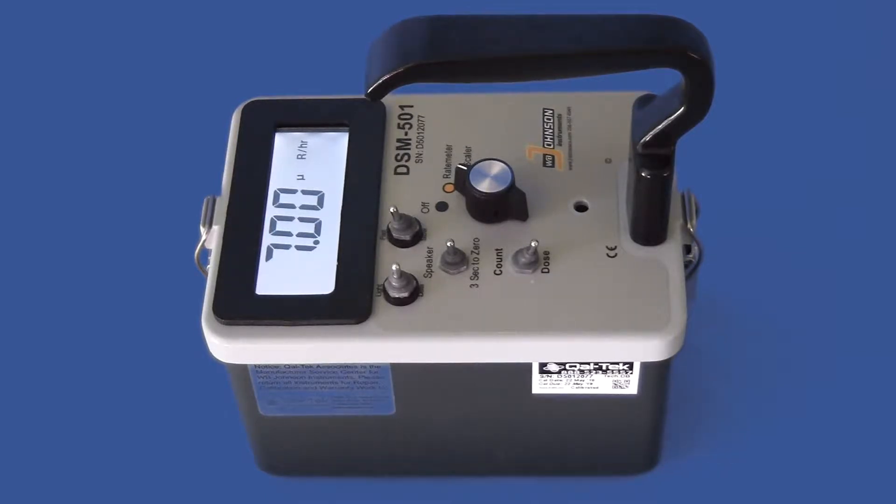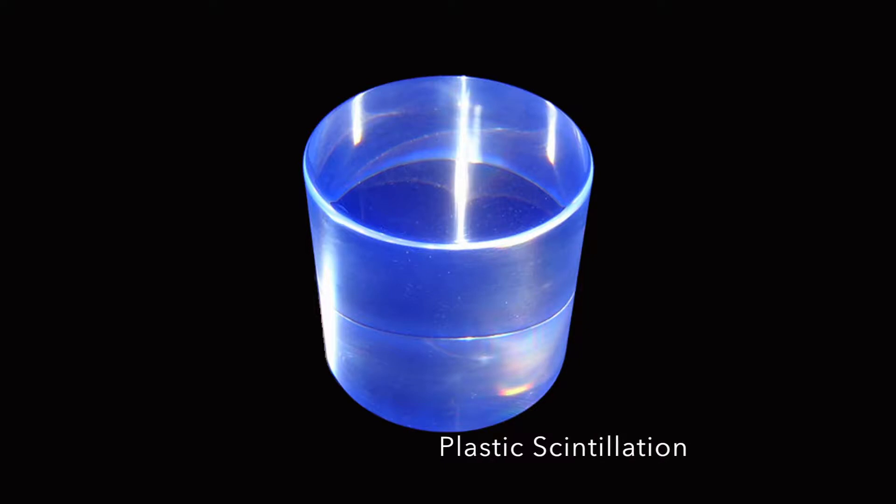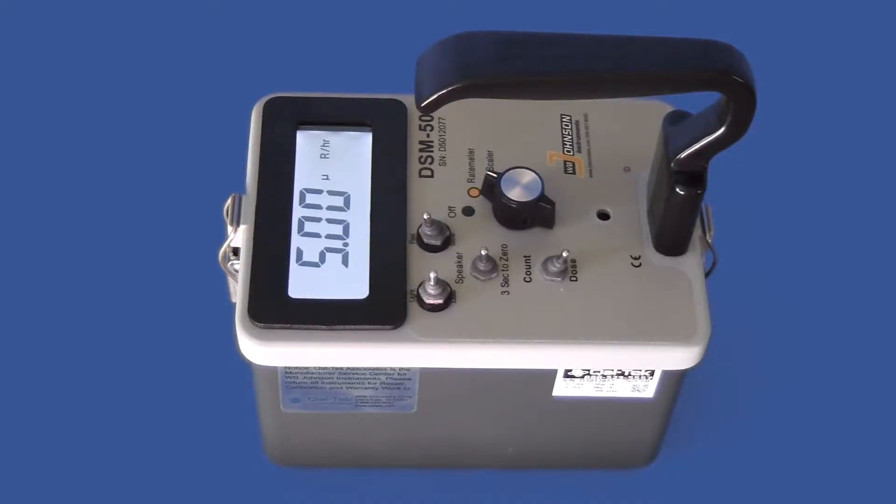This microroentgen meter features plastic scintillation which is ideal for dose measurement because it is near tissue equivalent. The DSM-501 features rate meter mode which measures in dose and counts, and scalar mode measuring counts over a set time interval.